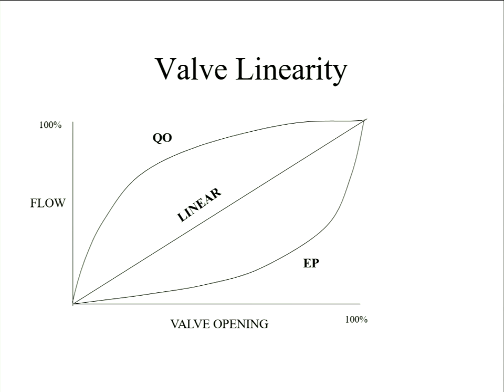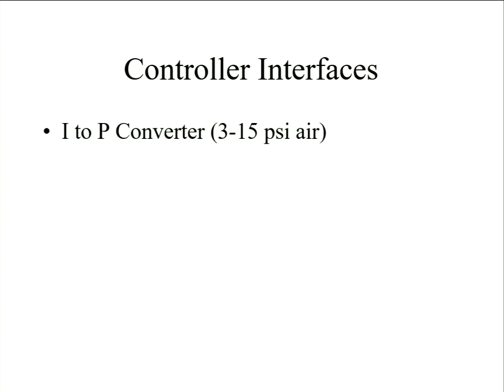Stepper motors, I'm not sure whether there are many, but historically at one time there were quite a lot of those in the gas industry, more associated with gas holder stations. This is an example of a control valve that's got an external controller and then a position actuator. As you put a current pressure loading into here, that's moving that valve up and down and controlling its position.